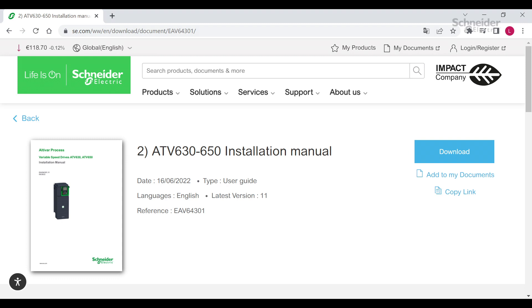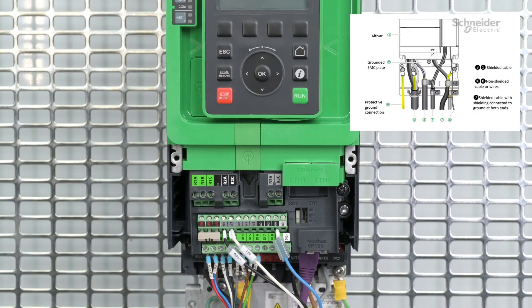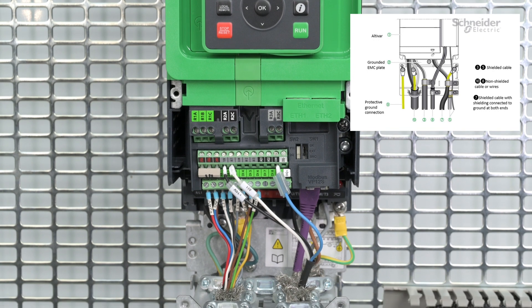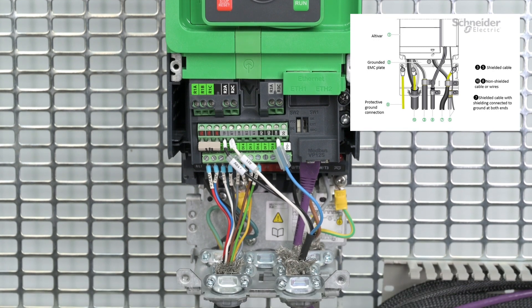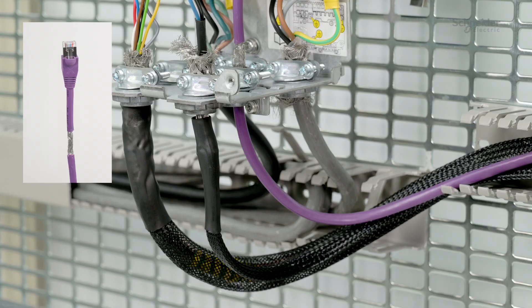You can download it on www.se.com. To summarize, to avoid EMC disturbance, it is mandatory to connect the motor cable shield to the ground. Both the product and the PLC must be connected to the ground. The shielding of the motor cable must be connected to the EMC plate of the product. The shielding of the fieldbus cable must be connected to the EMC plate of the product and to the PLC.